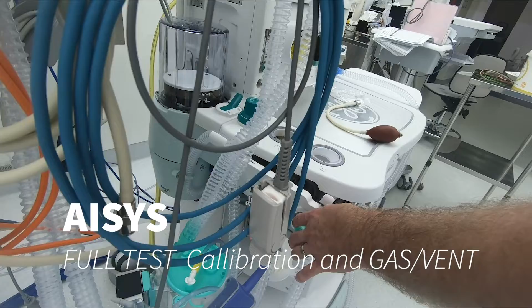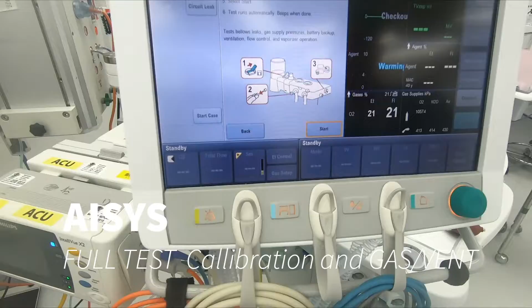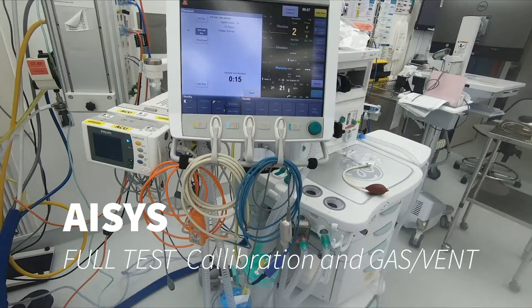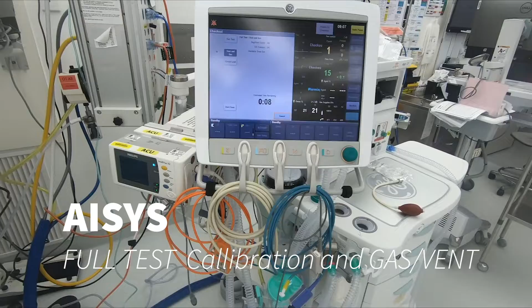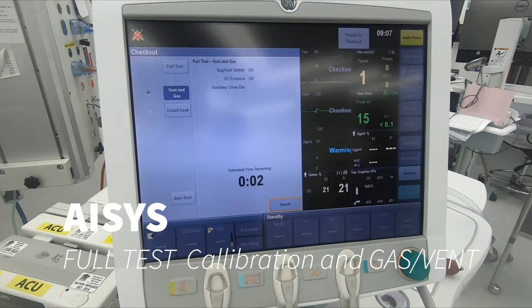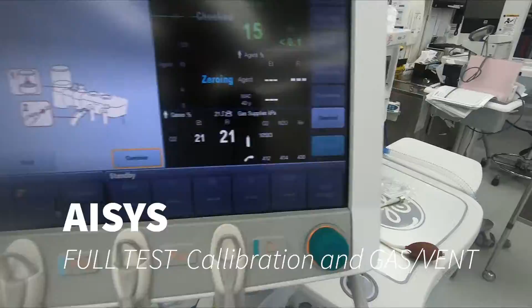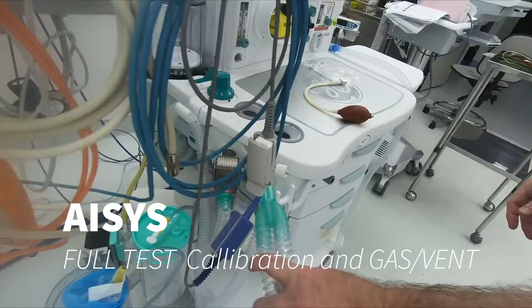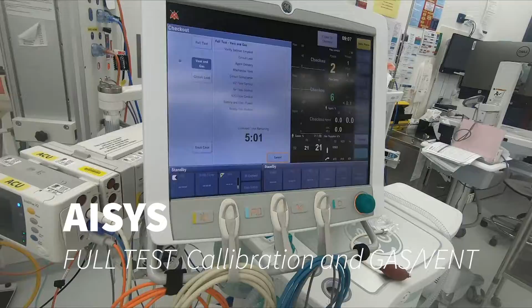Remove it. Ding. There's the signs come up. And it's calibrated. And we go to start, don't we? Yes. So it's doing the ventilator and manual test now. It's pretty straightforward, I remember. Make sure the bellows are fully collapsed. There we go. Occlude the patient Y, so yep, there we go. There's a slot on the side. Perfect. And then continue. So 5 minutes.